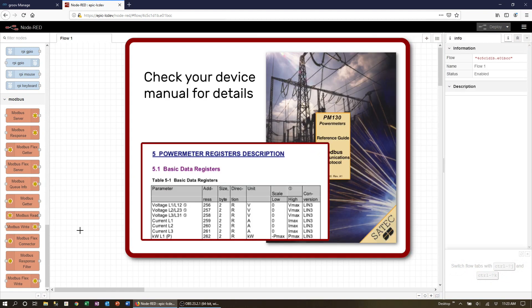Once the node is installed you will find it in your node palette on the left. Let's start with the voltage measurement. We can see in the manual that the phase 1 voltage register is 256. It is a read-only register so we need the Modbus read node.